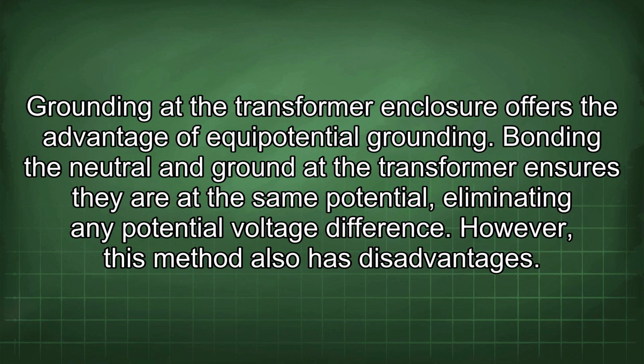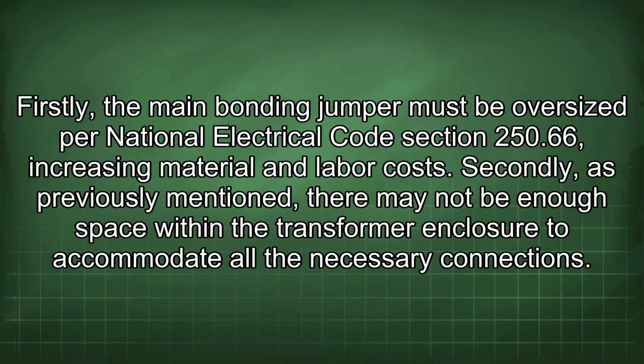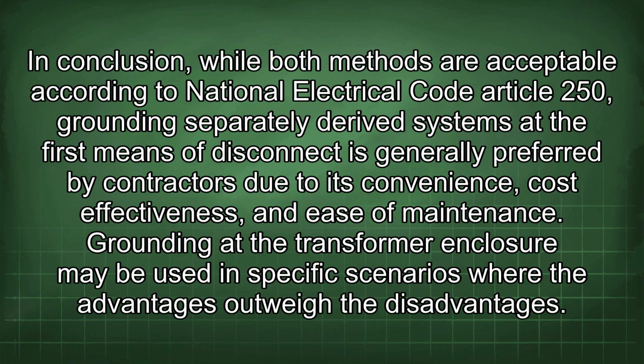However, this method also has disadvantages. Firstly, the main bonding jumper must be oversized per National Electrical Code Section 250.66, increasing material and labor costs. Secondly, as previously mentioned, there may not be enough space within the transformer enclosure to accommodate all the necessary connections. In conclusion, while both methods are acceptable according to National Electrical Code Article 250, grounding separately derived systems at the first means of disconnect is generally preferred by contractors due to its convenience, cost-effectiveness, and ease of maintenance. Grounding at the transformer enclosure may be used in specific scenarios where the advantages outweigh the disadvantages.